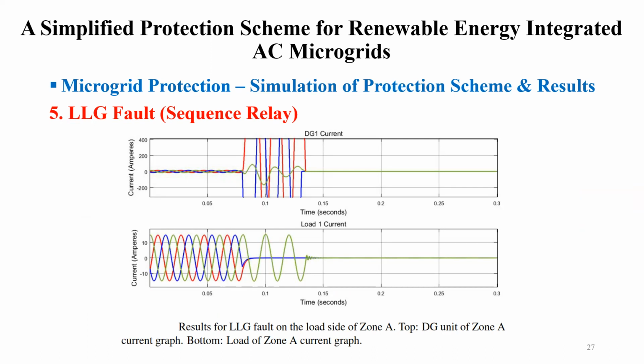once the fault comes on a distribution grid current, the effect is that once the sequences are unbalanced, we need to disconnect the distributed generation from the network. This is what we have seen. As soon as the fault arrived, within 0.1 seconds, the distributed generation is disconnected from the supply, and the grid is saved and protected.